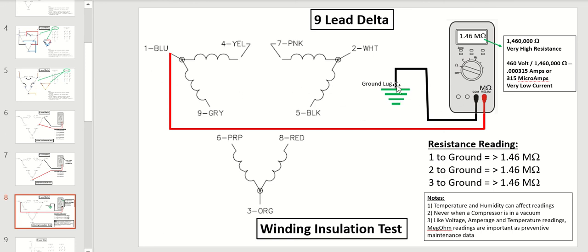And we do that by connecting the common lead of a megohm meter to the ground lug in the motor terminal box, and then we read to terminal 1, terminal 2, terminal 3, and make sure that we don't see anything less than, for a 460 volt motor, 1.46 megohms, which is actually 1,460,000 ohms, very, very high resistance. And if you did have 460 volts at that high of a resistance, the actual amperage would be very low, 315 microamps, or 0.000315 amps, very, very low current.